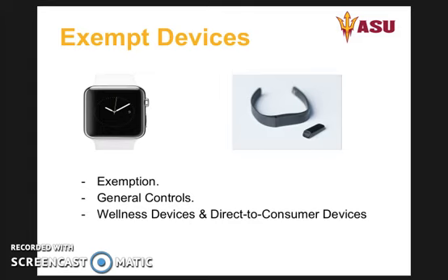Even exempt devices must meet the FDA's general controls, requiring companies to register their facilities with the FDA, submit forms describing the device and classification, adhere to labeling and packaging standards, and comply with quality systems regulations, or QSR. Some regulatory strategies avoid or delay FDA clearance and approvals by focusing on wellness, fitness monitoring, and similar non-medical applications that allow them to market their products directly to consumers.